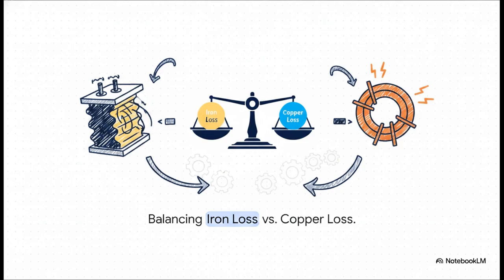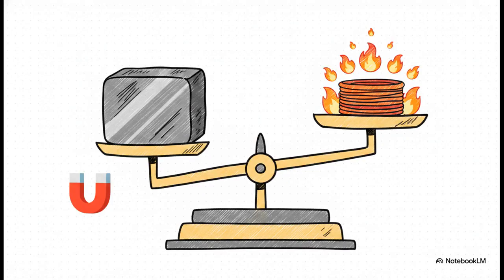To keep our power from draining away, we rely on routine maintenance. Things like using a TTR meter to make sure the turns ratio is spot on, or Megger testing to verify that our insulation is sitting safely above 1,000 megaohms. But here's the thing. Even with absolutely perfect maintenance, you're constantly fighting a battle between two types of unavoidable energy losses that dictate the overall efficiency of your plant. It is so crucial to understand the difference here.